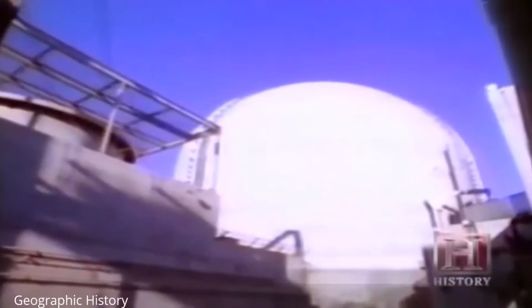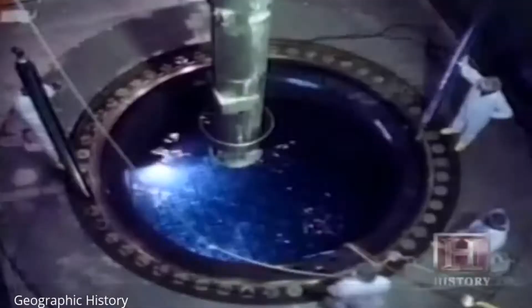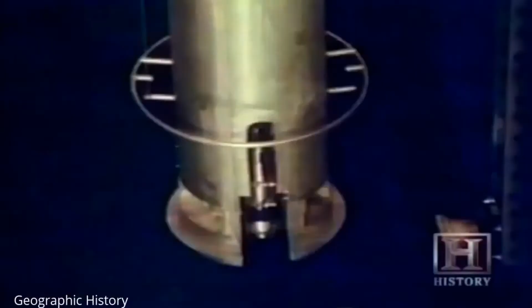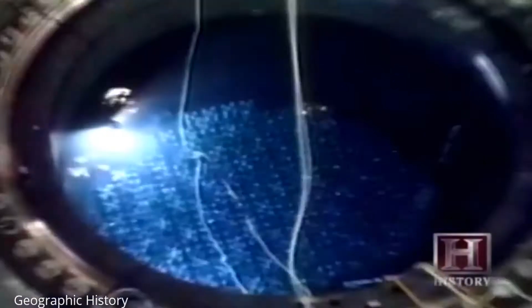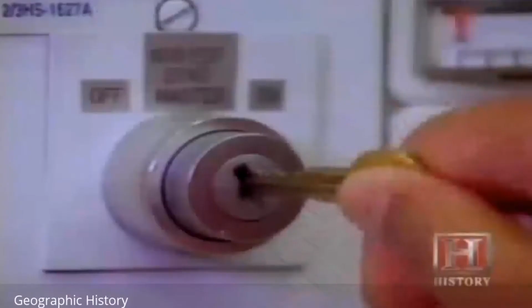But the surprising aspect of this plant is that, to a great degree, it runs without stopping. It can run for 2 years without needing new fuel at full output. San Onofre Unit Number 2 has been operating for about 530 days consecutively. If this were a natural gas, oil, or coal plant, we'd constantly need trains or pipelines bringing in fuel.